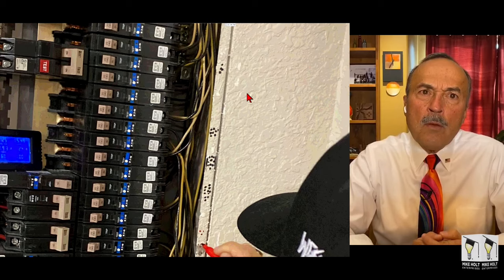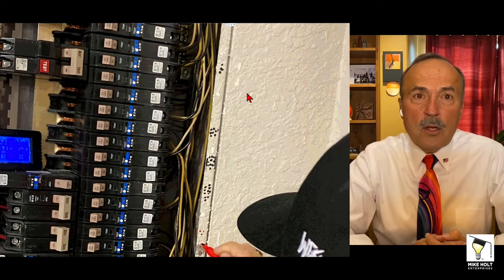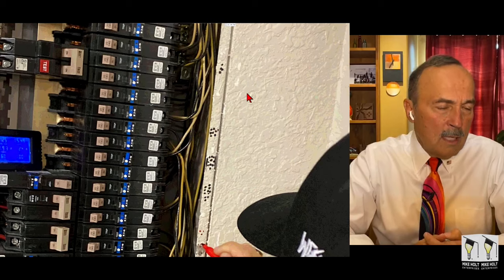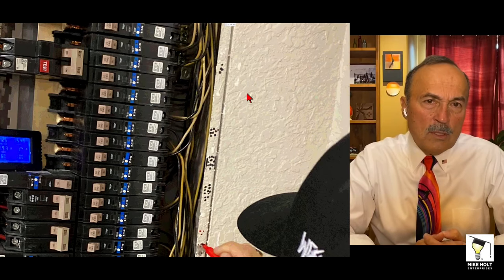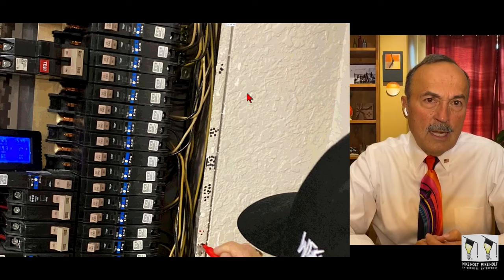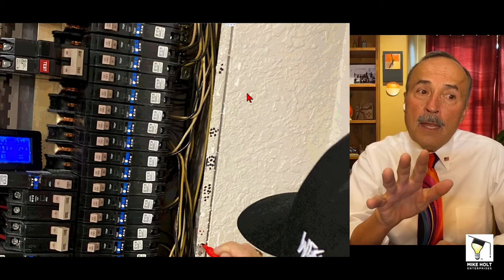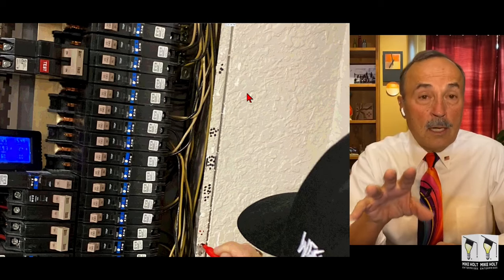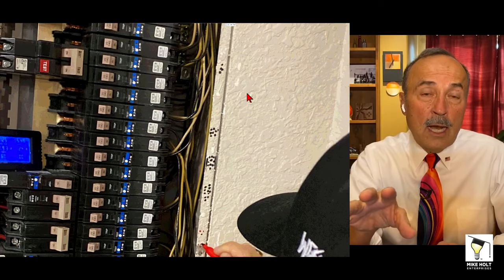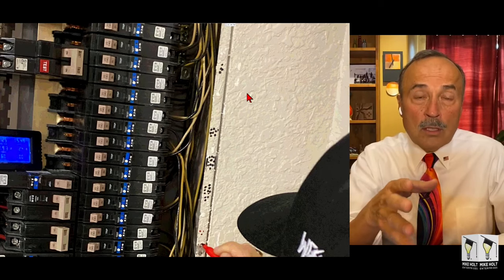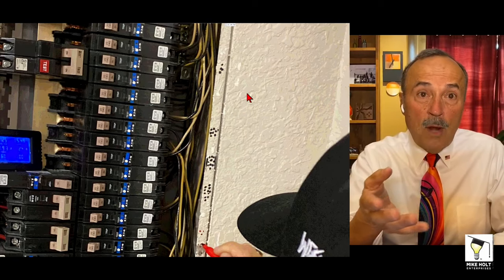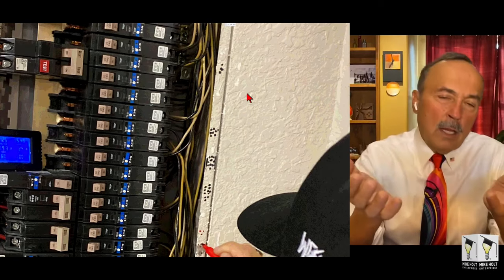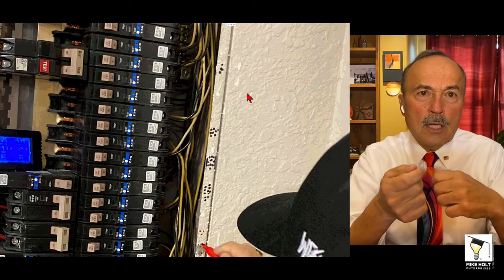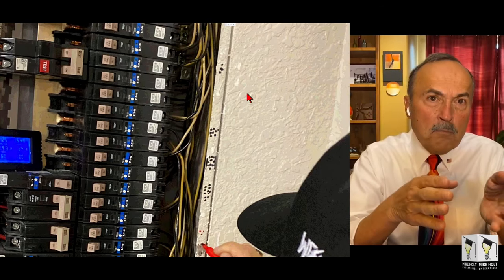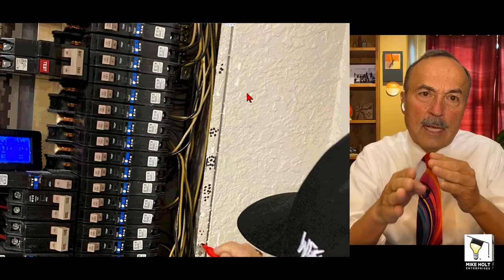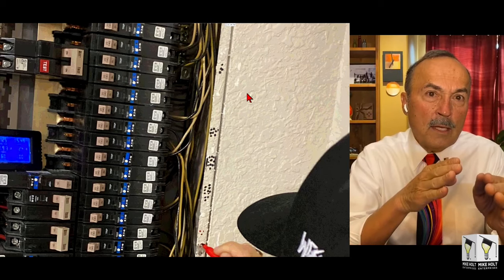What was my point? Well, number one, if somebody calls you about AFCI tripping, don't go in and start taking switches apart and receptacles apart, trying to troubleshoot this thing. Now, I'm talking about not a brand new installation. In a brand new installation, there could be some wiring errors. I'm just talking about an installation that works. If the breaker is working, then it's fine. That means there's no problem. Then it trips. Now, if clearly they say, when I turn on this light, it trips the breaker, well, then that's fine. But in the absence of an event causing the protection device to open, it just randomly happens.